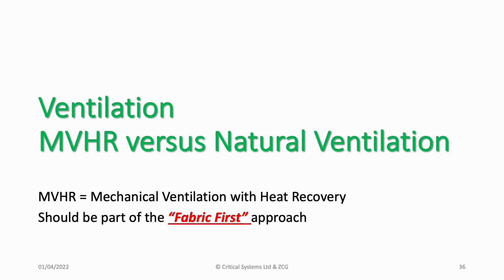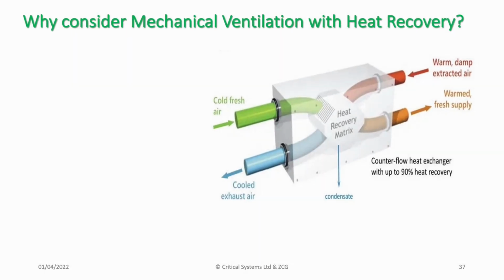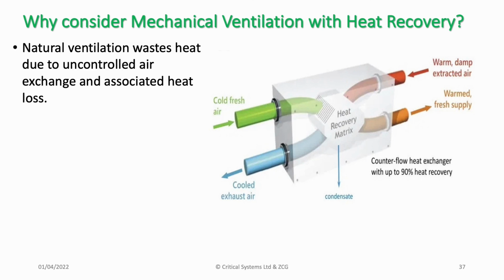I want to just look now at mechanical ventilation versus natural ventilation, and this is part of the fabric first approach. So why consider mechanical ventilation and heat recovery? And this is an indication of the configuration of such a heat recovery unit, and you can see in the centre of it is a cross-flow plate heat exchanger that exchanges heat from warm, moist exhaust air and imparts it to the incoming fresh air. And it is a heat recovery that can recover somewhere between 80 and 90% of the energy in the exhaust air. So natural ventilation wastes heat due to uncontrolled air exchange.